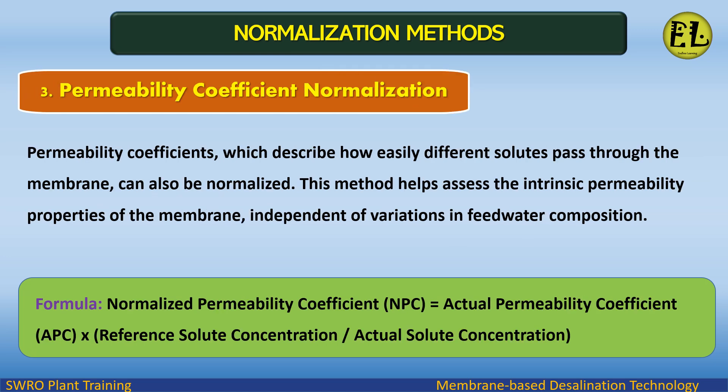Permeability coefficient normalization: permeability coefficients, which describe how easily different solutes pass through the membrane, can also be normalized. This method helps assess the intrinsic permeability properties of the membrane, independent of variations in feedwater composition. The formula is: Normalized Permeability Coefficient (NPC) = Actual Permeability Coefficient (APC) × (Reference Solute Concentration / Actual Solute Concentration).